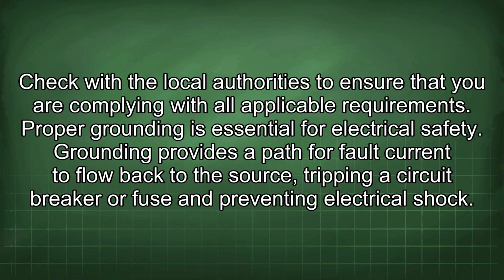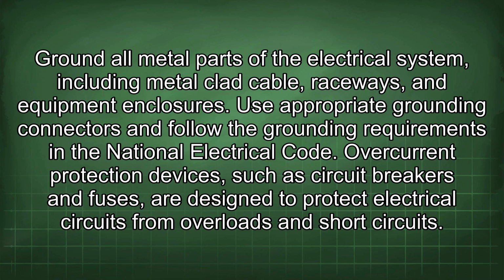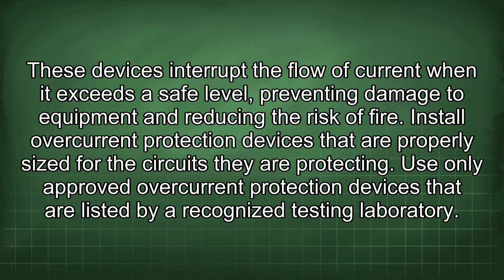Proper grounding is essential for electrical safety. Grounding provides a path for fault current to flow back to the source, tripping a circuit breaker or fuse and preventing electrical shock. Ground all metal parts of the electrical system, including metal-clad cable, raceways, and equipment enclosures. Use appropriate grounding connectors and follow the grounding requirements in the National Electrical Code. Overcurrent protection devices, such as circuit breakers and fuses, are designed to protect electrical circuits from overloads and short circuits. These devices interrupt the flow of current when it exceeds a safe level, preventing damage to equipment and reducing the risk of fire. Install overcurrent protection devices that are properly sized for the circuits they are protecting. Use only approved overcurrent protection devices that are listed by a recognized testing laboratory.